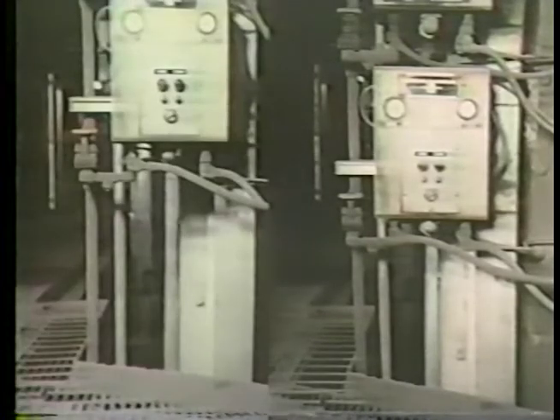Unless this expansion occurs evenly, the boiler casing, water wall tubes, headers, and other components may be damaged or even rupture. This can create a safety problem in the plant and affect the useful life of the boiler. By the same token, during shutdown, the metal components contract as their temperatures decrease. Contraction must also occur evenly to prevent damaging components. The expansion and contraction of boiler components is caused by the pressures and temperatures under which the boiler operates. Firing rate is the control that an operator has over temperature and pressure.